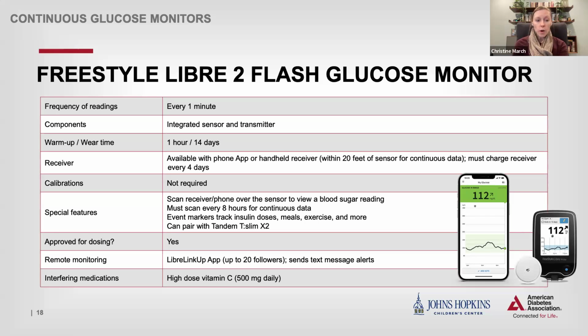Calibrations are also not generally required, though you may be prompted to calibrate. And in this case, you would scan either your phone or the receiver over your sensor to see the sugar reading. And if you scan at least every 8 hours, you will get a continuous data tracing. If you don't scan every 8 hours, then at some point you just won't see that tracing, but it will come back when you scan again. This also has event markers, and it can pair with the Tandem T-Slim pump, but I personally have not had any patients using this combination. It is also approved for dosing. You can have up to 20 followers with their app, the Libre Link Up, and that can include text message alerts to your followers. And the company states that high-dose vitamin C may interfere with its accuracy.